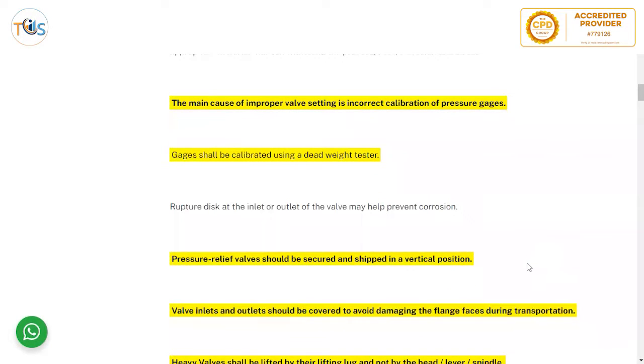The main cause of improper valve setting is incorrect calibration of pressure gauges. Gauges shall be calibrated using a dead weight tester. A rupture disc at the inlet or outlet of the valve may help prevent corrosion, by preventing the flow from reaching the spring and stem at the back of the valve.